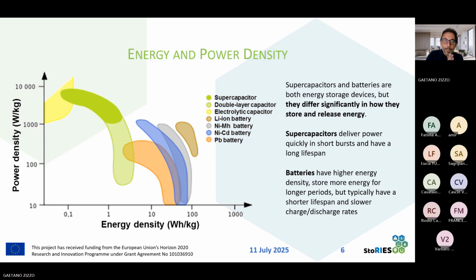On the contrary, if we examine the graph, we can see that the energy density of the batteries represented in this case is usually over 2 watt-hours per kilogram, and can reach for lithium-ion batteries also 200, 300 watt-hours per kilogram, but the power density usually is not over 1000 watts per kilogram. So different characteristics and different applications, and so for each specific application of a storage system connected to the grid, we will have to choose the right technology able to deliver a given service.